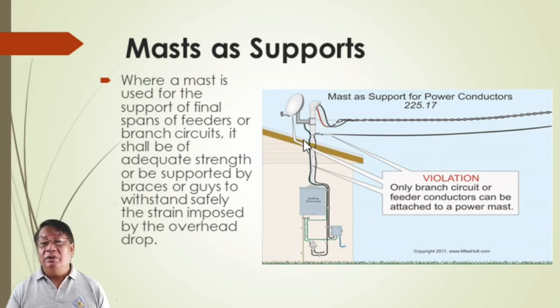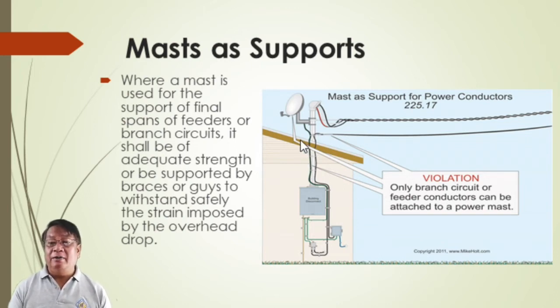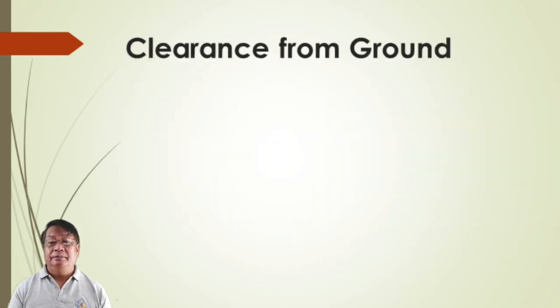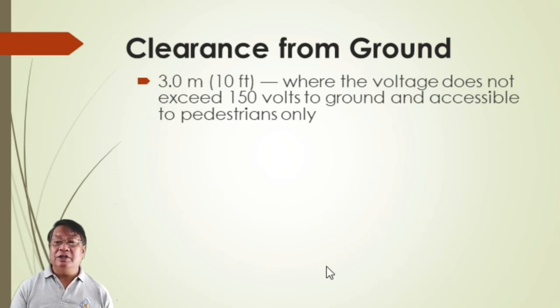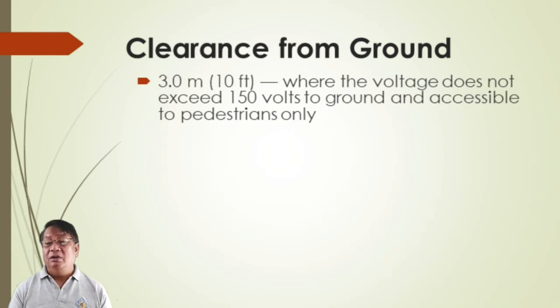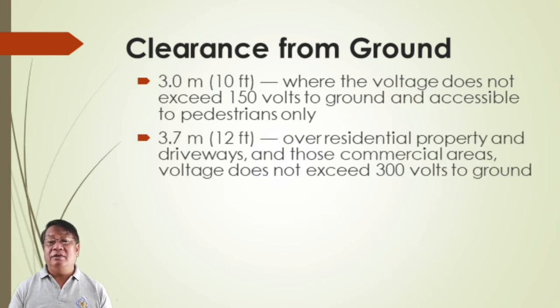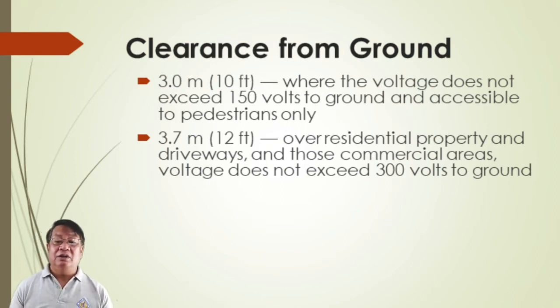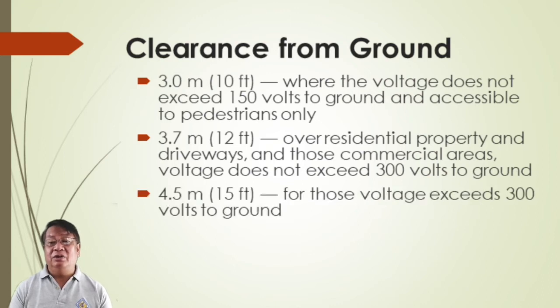For clearance from ground where voltage does not exceed 150 volts to ground and accessible to pedestrians only: 3.7 meters or 12 feet over residential property and driveways. For commercial areas where voltage does not exceed 300 volts, 12 feet or 3.7 meters is required. If more than 300 volts, it should be more than 4.5 meters or 15 feet.